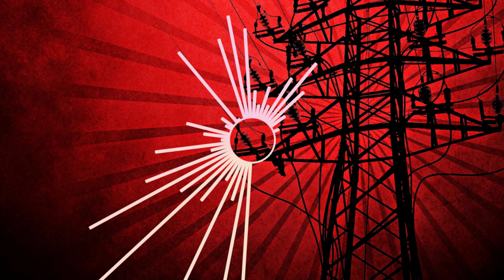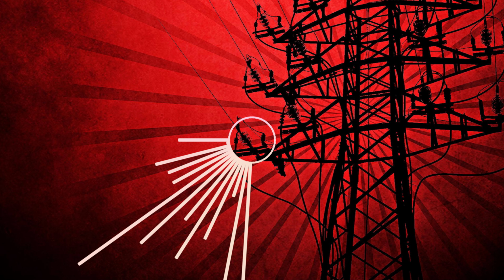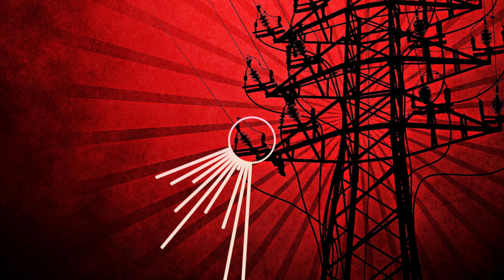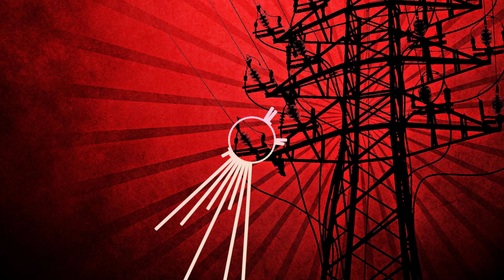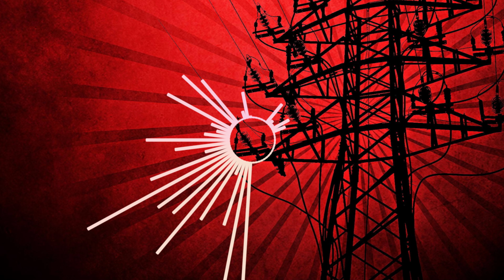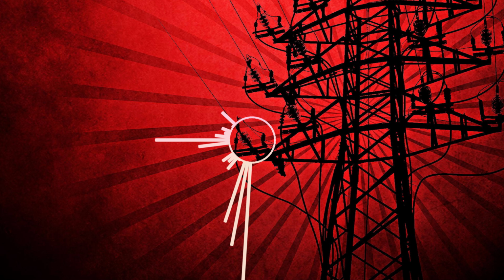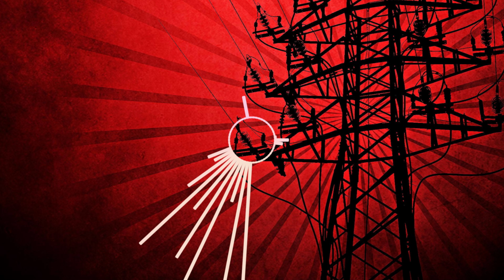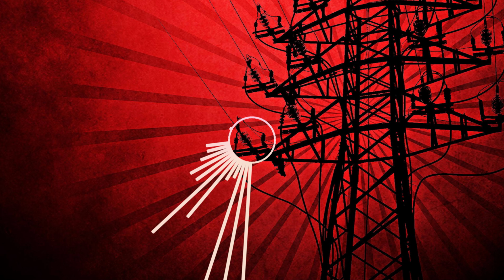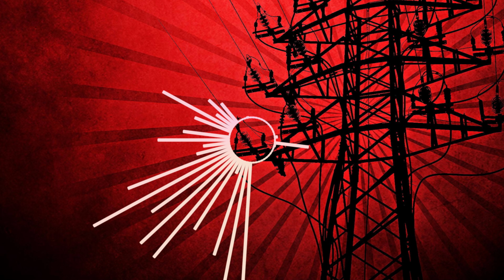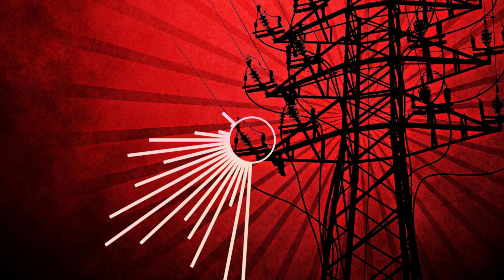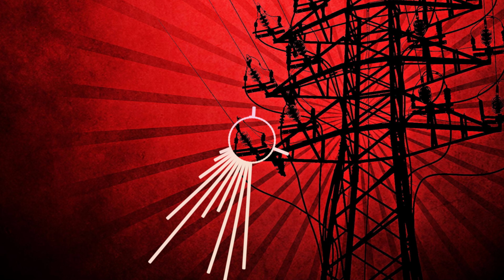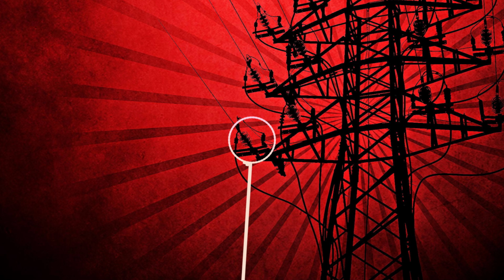For circuits rated over 100 amps, or for wires larger than 1 American wire gauge, you need to use conductors rated 75 degrees Celsius. You can use higher rated conductors such as those rated for 90 degrees Celsius or 105 degrees Celsius, but the ampacity of those wires must be based on the 75 degree Celsius rating, unless equipment is specifically marked for the higher rated conductors.